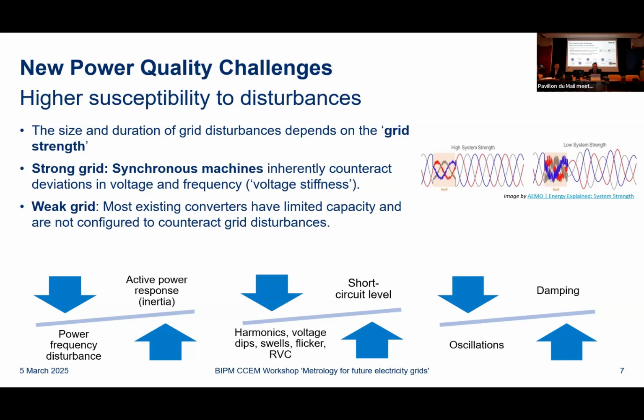But as the synchronous machines are going away, the grid is becoming weaker because most of the converters existing today are not grid forming. We heard Stefano talk about a new project to look at new types of converters, but most existing ones have limited current capacity and their control systems are not designed to provide this voltage stiffness. They actually look to the synchronous machines to provide that voltage stiffness. So not only do we have new disturbances, potentially a higher number of them, we've also got less inertia, less short circuit levels, so less fault current. We also have less damping, which is related to the extent to which those oscillations I mentioned persist in the grid.